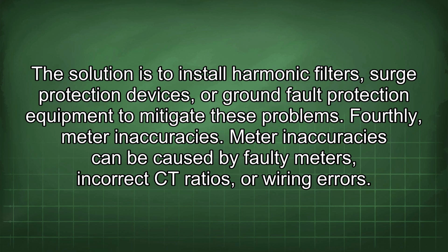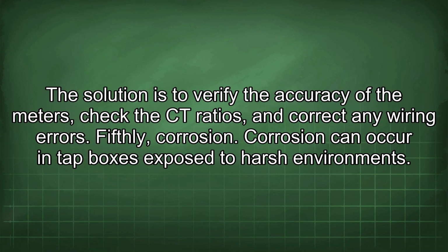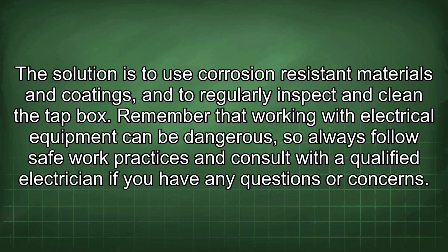Fourthly, meter inaccuracies. Meter inaccuracies can be caused by faulty meters, incorrect CT ratios, or wiring errors. The solution is to verify the accuracy of the meters, check the CT ratios, and correct any wiring errors. Fifthly, corrosion. Corrosion can occur in tap boxes exposed to harsh environments. The solution is to use corrosion-resistant materials and coatings, and to regularly inspect and clean the tap box.